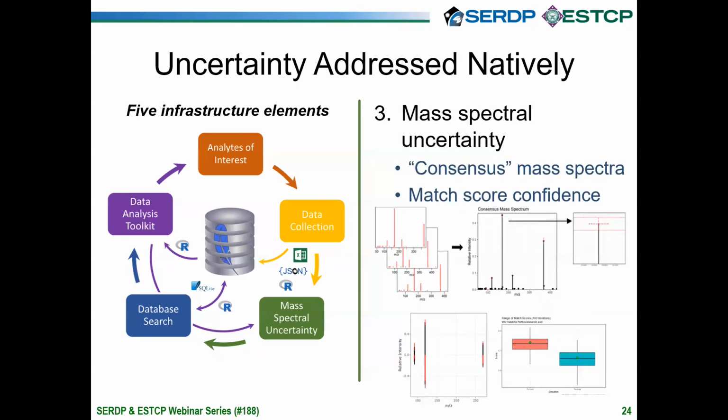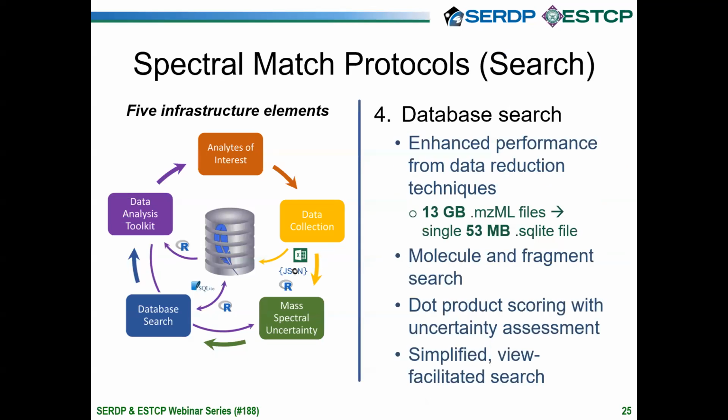Spectra were collected across each of those chromatographic peaks to build consensus or uncertainty-based mass spectra. Each scan is recorded in the database. There's always a bit of variability in both the mass to charge value and relative intensity across these peaks, and DIMSpec respects that uncertainty. These uncertainty spectra are then used by the toolkit to match new data against the library, and we can provide an uncertainty range around the resulting dot product rather than giving a single value.